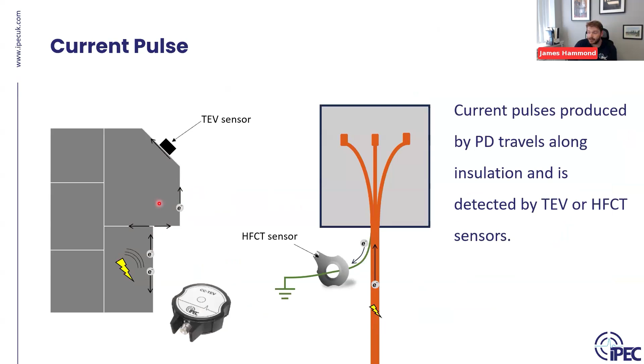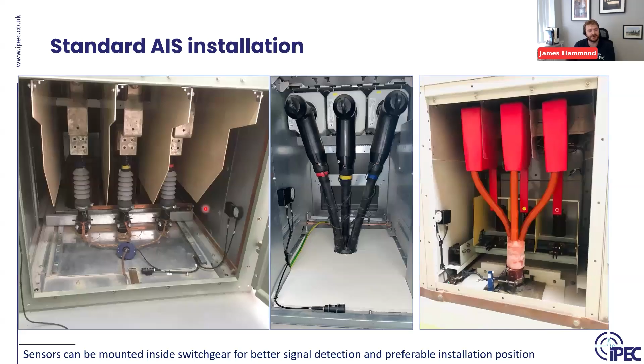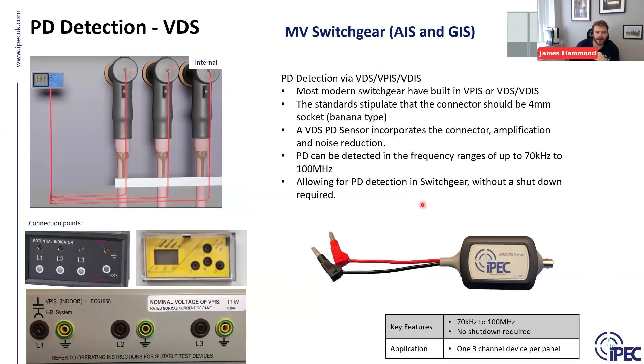And then if any of you are in renewables, we find that a lot of new gear is generally gas insulated, especially MV gas insulated gear. This has been notoriously difficult historically to test, mainly because the cabinets themselves are completely sealed, hermetically sealed. So getting a TeV signal out of there can be quite challenging. If you look here, there's small gaps in the cladding, but something that's hermetically sealed can be quite difficult. So sensors can be used there as well to plug directly into the existing VPIS, VDIS, whatever you call them, but the voltage detection system ports, they can be used as well as a method to detect partial discharge.